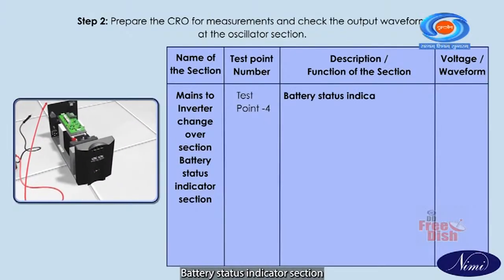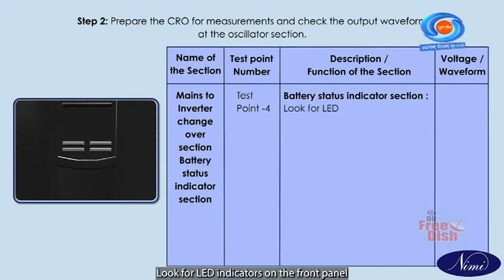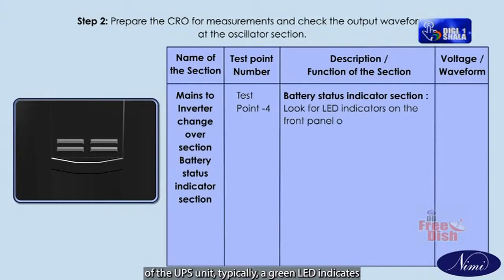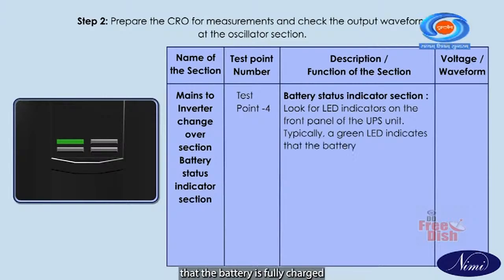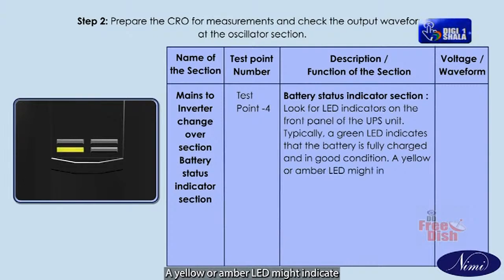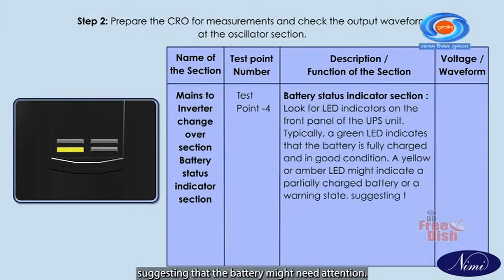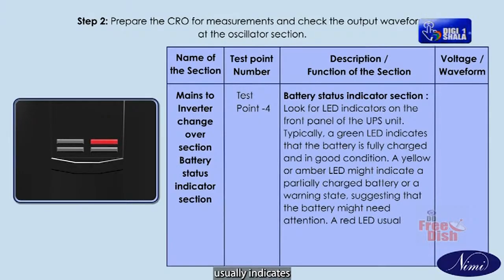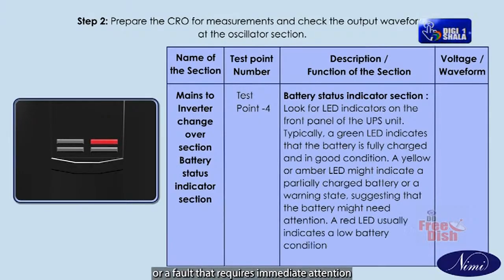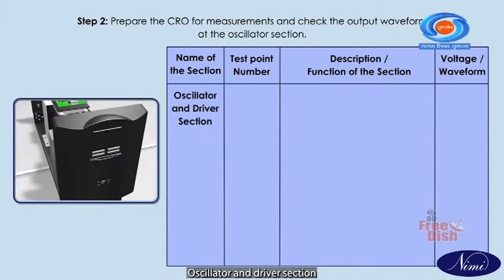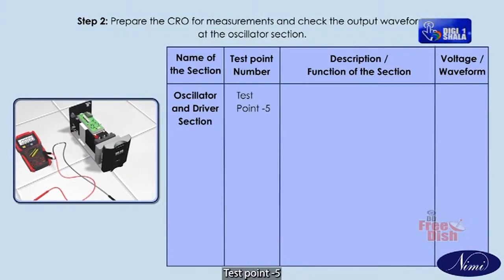Test point 4. Battery status indicator section. Look for LED indicators on the front panel of the UPS unit. Typically, a green LED indicates that the battery is fully charged and in good condition. A yellow or amber LED might indicate a partially charged battery or a warning state, suggesting that the battery might need attention. A red LED usually indicates a low battery condition or a fault that requires immediate attention. Oscillator and driver section.